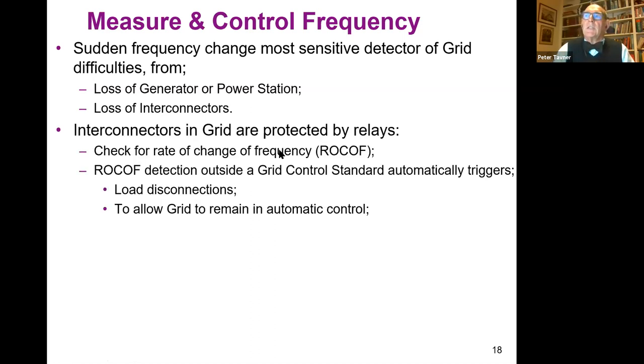Now, the interconnectors in the grid are protected by electrical relays. They can interrupt a transmission line, and those relays check all the time for the rate of change of frequency. In the industry, we call it ROCOF, rate of change of frequency. They're called ROCOF relays, and ROCOF detection is vitally important to protect grids in all our countries.